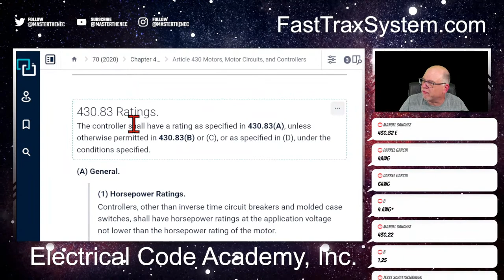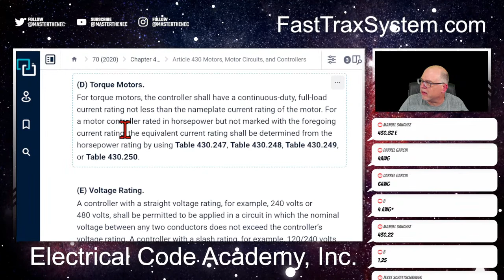It has voltage rating in the question. The manual has a reference in there. So we're looking at A. That's not relevant. That's not relevant. Voltage rating, that was actually in the question. Now, quickly, I'm looking at it, and I'm saying a controller with a straight voltage rating, which is what ours was, a straight 480. For example, 240 volts or 480 shall be permitted to be applied to the circuit in which the nominal voltage between any two conductors does not exceed the controller's voltage rating.